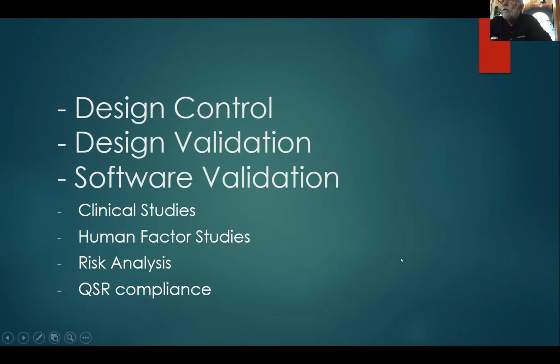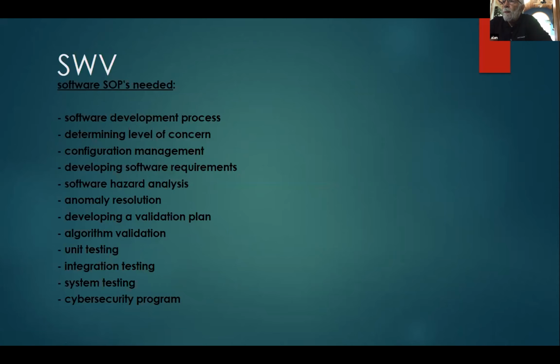So what is software validation? Software SOPs are needed. You should have procedures for the software development process, determining the level of concern of your software, configuration management, and developing software requirements. What is the software hazard analysis? How do you determine that and put it through a hazard analysis? You have to have anomaly resolution, developing a validation plan, the algorithm validation, unit testing, integration testing, system testing, and then a cybersecurity program. You need this if you're involved in AI. You need this as part of your software validation.